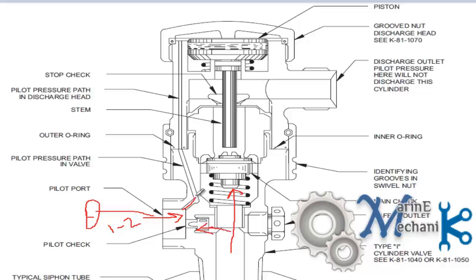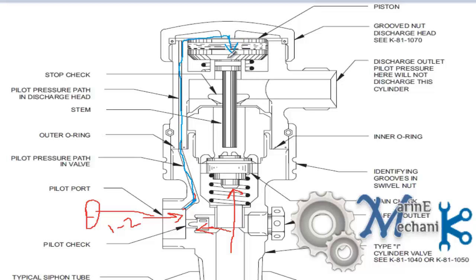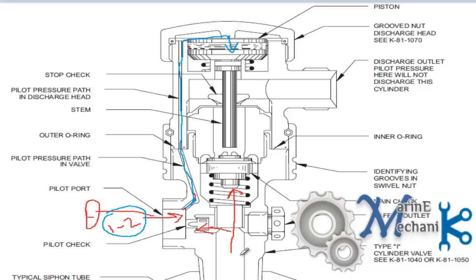So it will travel through this path. Just trace out this blue line. It will travel through this path. It climbs up, goes and then goes here and activates this piston. The piston moves down. You must wonder how does the lesser pressure CO2 can open this valve against higher pressure CO2 inside the bottle. It is very simple. The idea is having a large area piston.